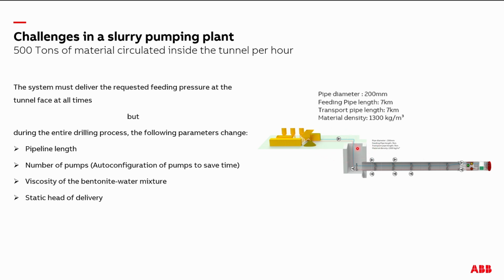The main duty is that the tunnel boring machine driver tells the slurry pumping plant to create so much pressure as counter pressure, and the rest has to be done with the AC500. So the AC500 needs to know: what's the pipeline length at the moment, and how many pumps are activated at the moment?